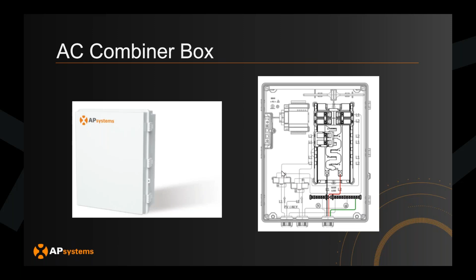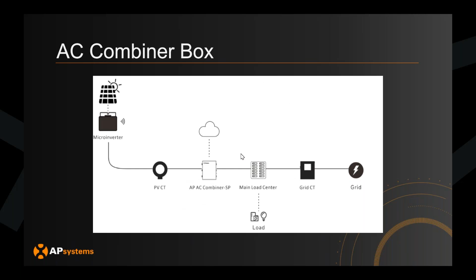Electrically, you have the combiner box here, where your microinverters land inside the AC combiner box. Power then goes from the combiner box to your main load center. From the CT perspective, there are internal CTs where the solar strings go in, and external grid CTs between the main panel and the meter to measure import and export power from the system.